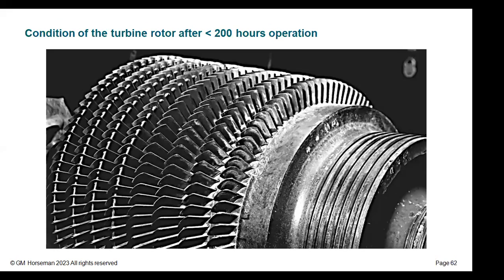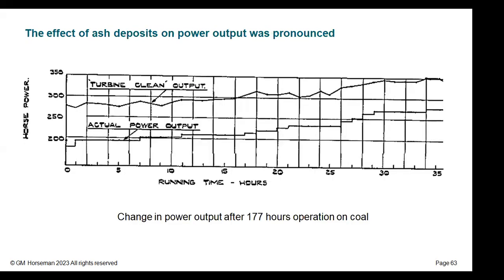So, and that's the turbine rotor after 200 hours. So you don't have the same notch effect because the particles go to the outer boundary, not the inner. But nonetheless, you still have the same issues of buildup occurring and chemical attack. So down to only 2 slides, I think, at this point. To the left, this is what happened to the power output. If you see the top curve as being for those conditions that existed, had the machine been clean, that's what you would have achieved. And the lower line is what happens when you try to achieve it, passing coal through. You're basically at half the output of the machine. And that's with the buildup of only 50 hours, 100 hours of operation.